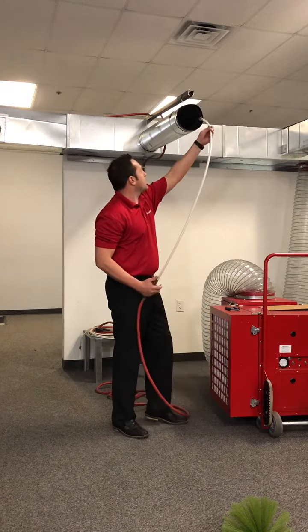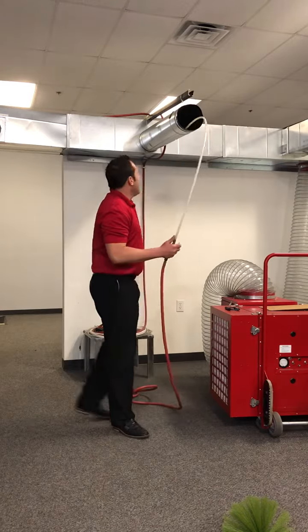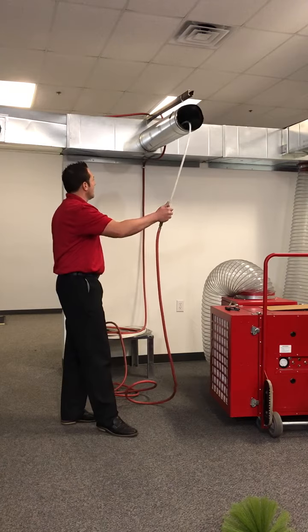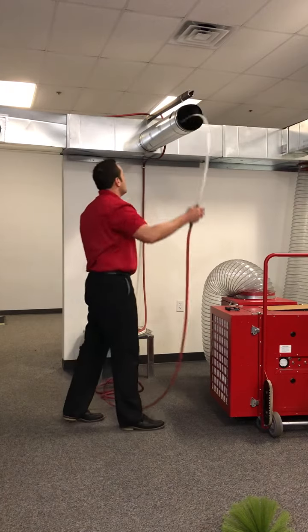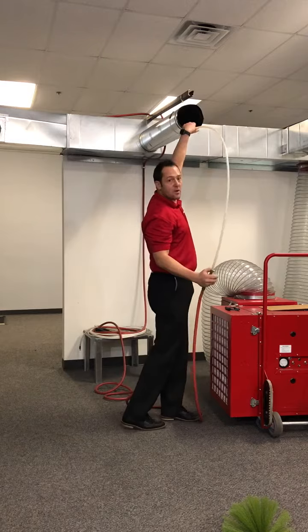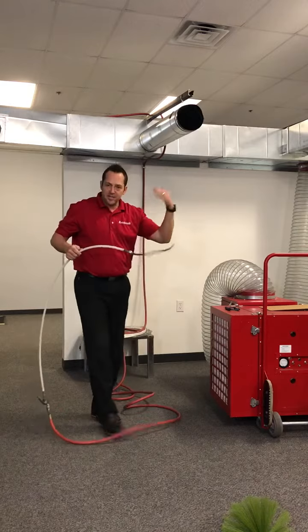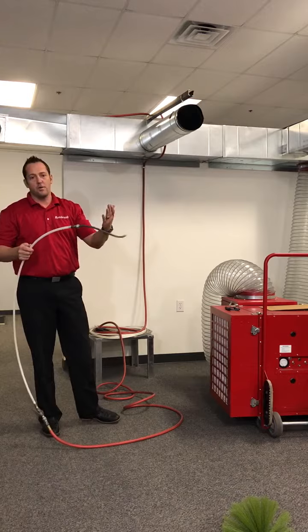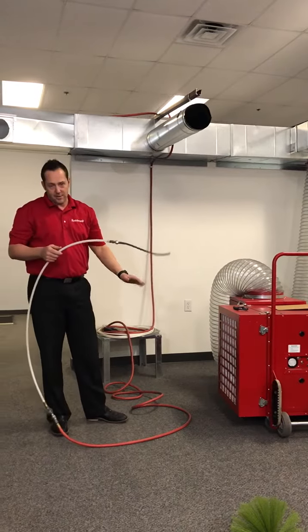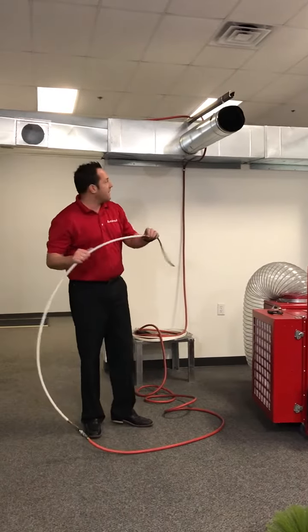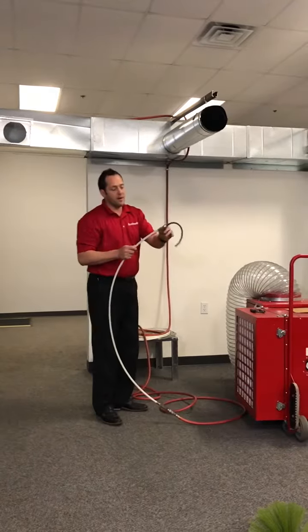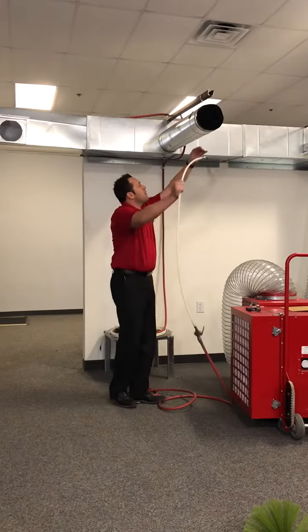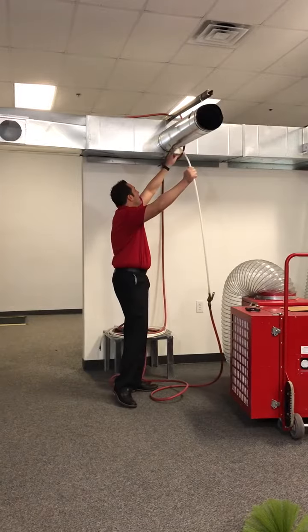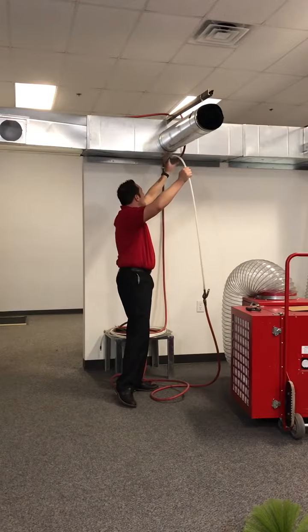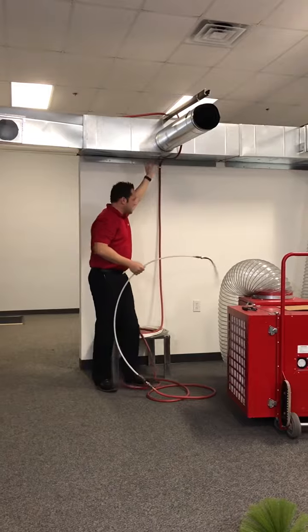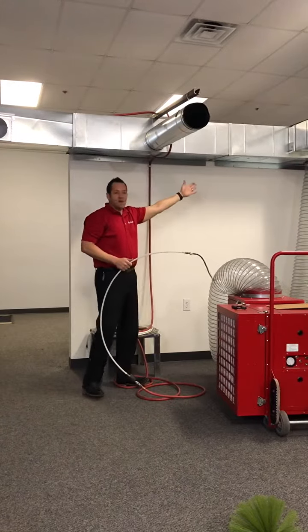Now again, you're coming back through with your compressed air. As it goes, it's just going to bounce around inside of the ductwork itself, agitating inside of it, airborne, and then blowing the dust and debris back to the actual access hole itself. Now in this case, I'm using a forward air sweep, so the hole's in the front of it. As I'm going through, that dust and debris is blowing this way, in addition to the agitation, blowing into my main trunk line. Once it hits your main trunk line, it's going to be vacuumed up.